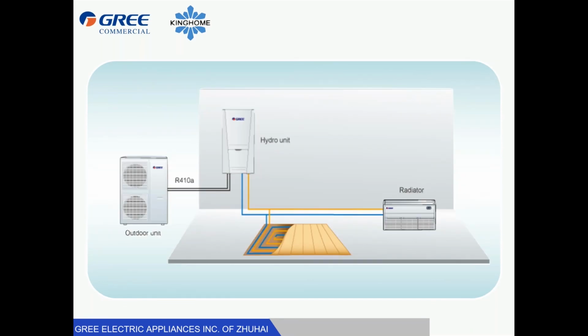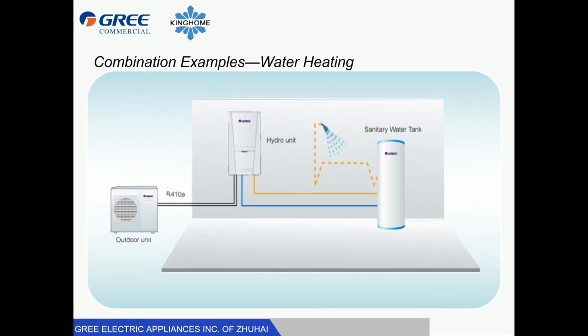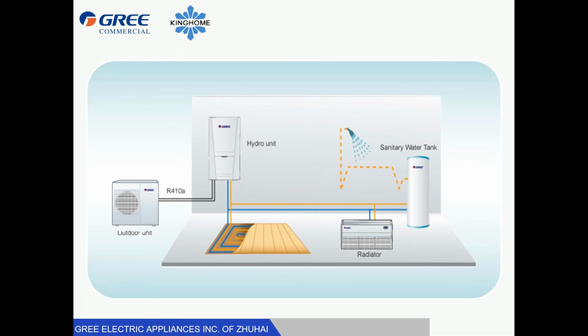Here's a simple diagram of a system that is just doing space conditioning, heating and cooling for space. Here's a simple diagram of a system that is doing domestic hot water. And here's a simple diagram of a system that would be doing both. Now, since these are only 54 MBH nominal, they're probably ideal for maybe smaller office buildings or residential use, something like that. We do have an 8-ton system that'll be coming out sometime next year. That'll be available soon. The 8-ton system also will have a 55-gallon water tank available with it.